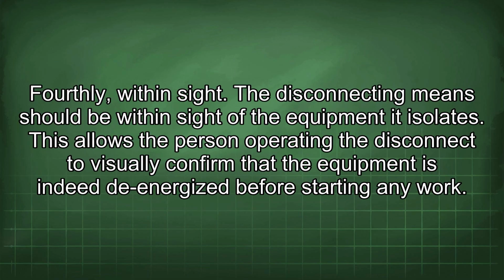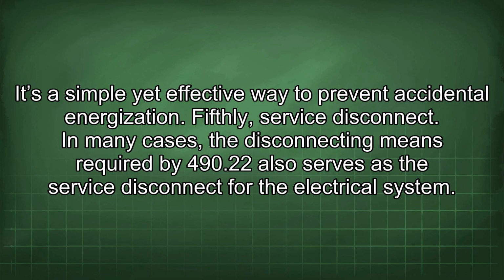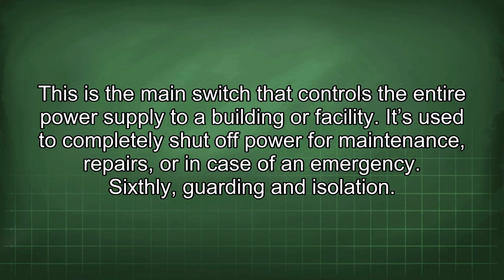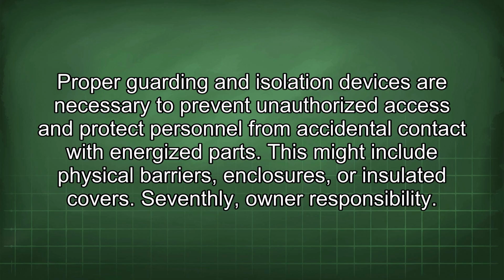Fourthly, within sight. The disconnecting means should be within sight of the equipment it isolates. This allows the person operating the disconnect to visually confirm that the equipment is indeed de-energized before starting any work. It's a simple yet effective way to prevent accidental energization. Fifthly, service disconnect. In many cases, the disconnecting means required by 490.22 also serves as the service disconnect for the electrical system. This is the main switch that controls the entire power supply to a building or facility. It's used to completely shut off power for maintenance, repairs, or in case of an emergency. Sixthly, guarding and isolation. Proper guarding and isolation devices are necessary to prevent unauthorized access and protect personnel from accidental contact with energized parts. This might include physical barriers, enclosures, or insulated covers.